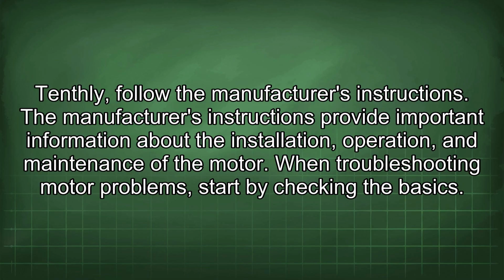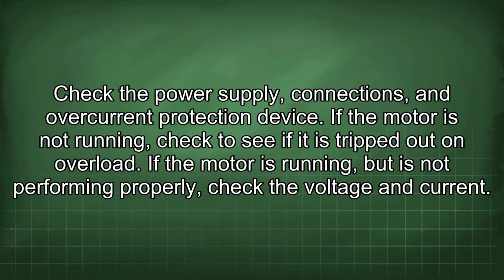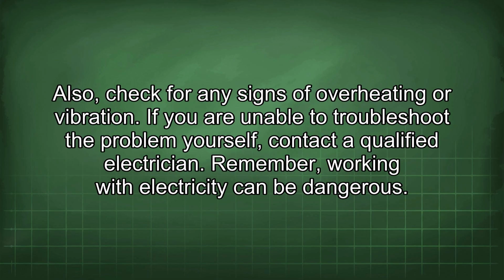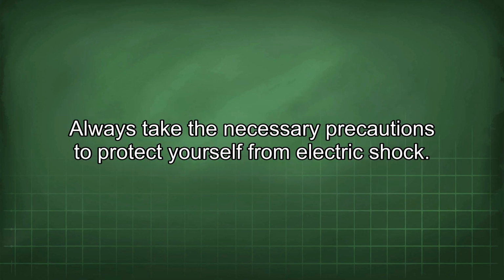When troubleshooting motor problems, start by checking the basics. Check the power supply, connections, and overcurrent protection device. If the motor is not running, check to see if it is tripped out on overload. If the motor is running, but is not performing properly, check the voltage and current. Also, check for any signs of overheating or vibration. If you are unable to troubleshoot the problem yourself, contact a qualified electrician. Remember, working with electricity can be dangerous. Always take the necessary precautions to protect yourself from electric shock.